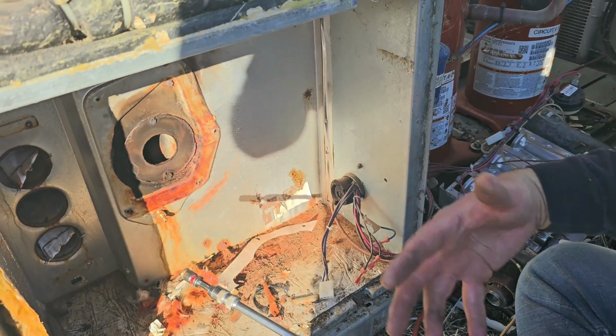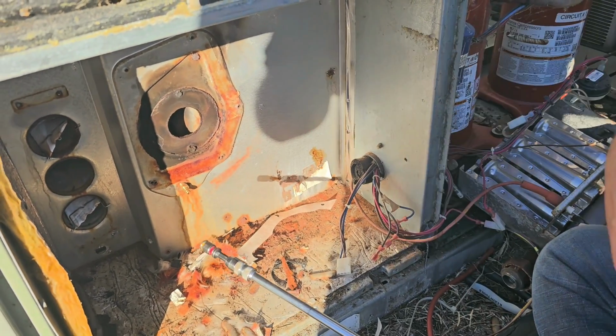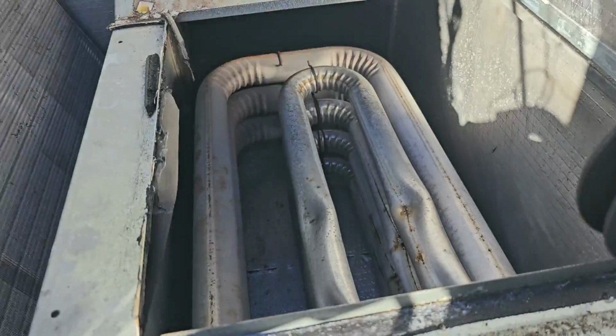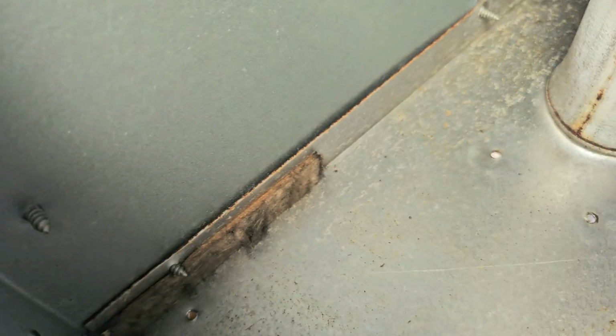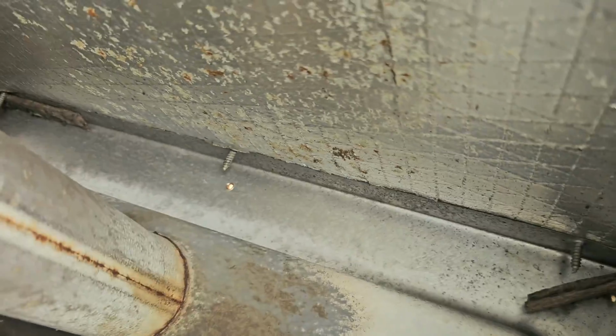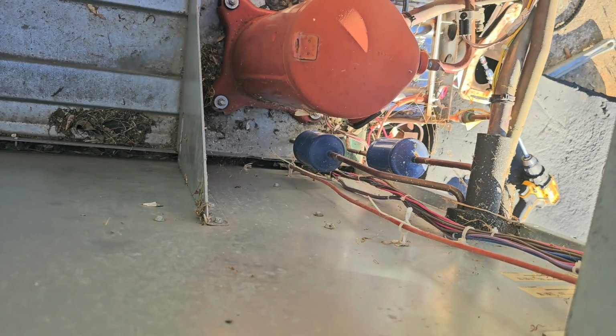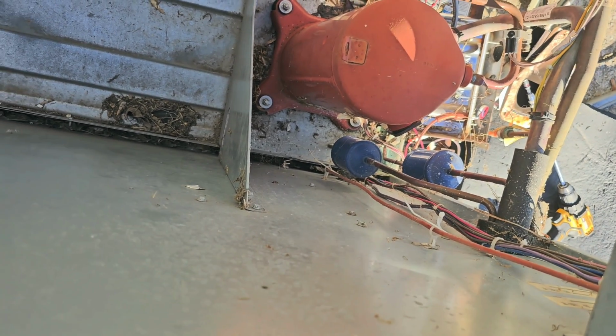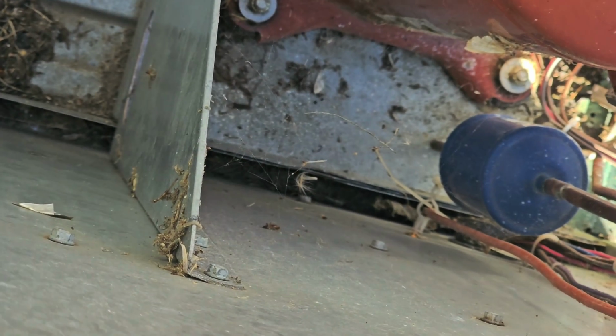I don't want them to be in the way when I pull the heat exchanger out, because I've got to pull it out this way. And I'm going to show you where the other screws are, because I don't think you've got it loose from just the front. See that screw there and that screw there? Those are right here. 1, 2, and then on the other side, 1, 2, 3. So you get to those from the condenser section. All right, so we need to get those out.